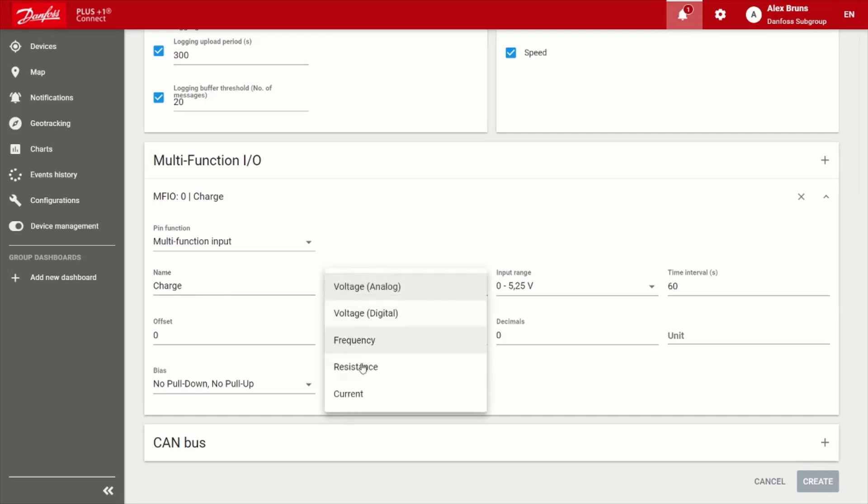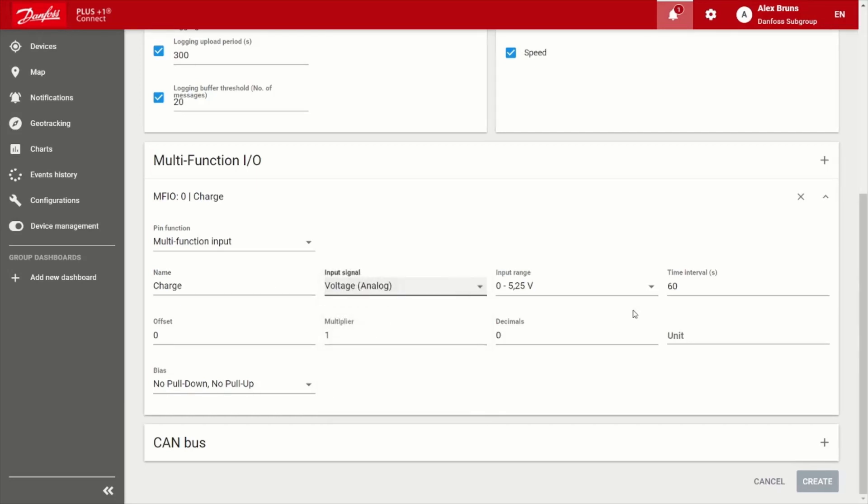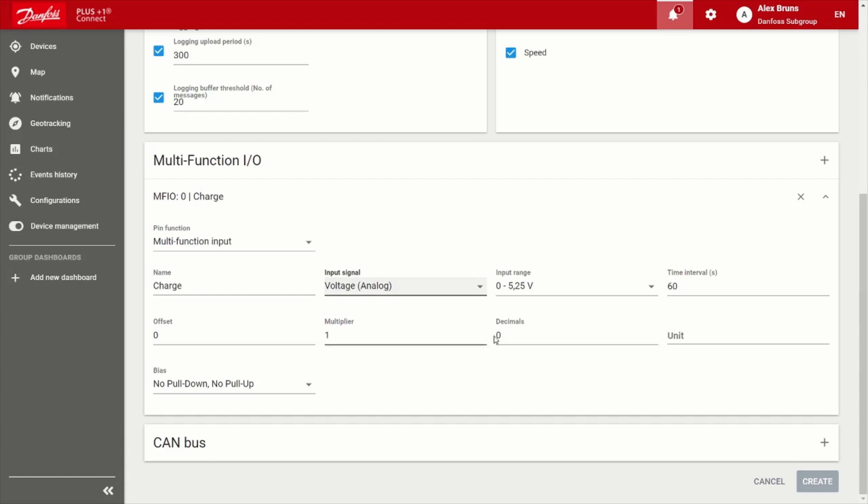Choose the signal, in this case, it would likely be an analog voltage input, choose the range, again, the time interval or frequency that you want that message to be captured. And then you can apply an offset and multiplier to give it engineering units. So it's human readable. And then of course, in this case, it would be bar or psi, for example.